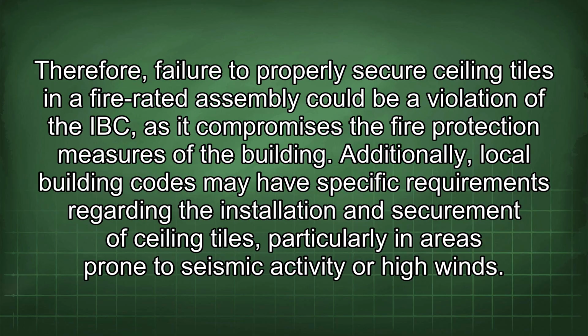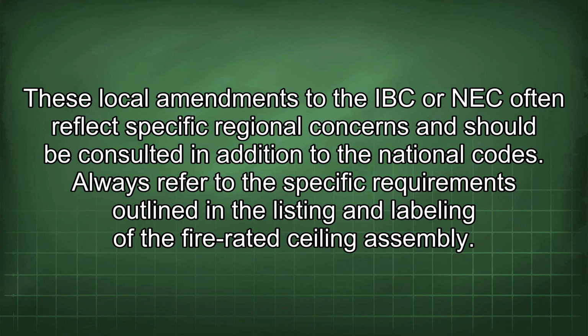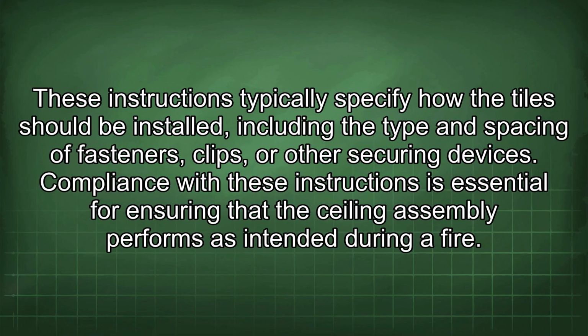Additionally, local building codes may have specific requirements regarding the installation and securement of ceiling tiles, particularly in areas prone to seismic activity or high winds. These local amendments to the IBC or NEC often reflect specific regional concerns and should be consulted in addition to the national codes. Always refer to the specific requirements outlined in the listing and labeling of the fire-rated ceiling assembly. These instructions typically specify how the tiles should be installed, including the type and spacing of fasteners, clips, or other securing devices. Compliance with these instructions is essential for ensuring that the ceiling assembly performs as intended during a fire.